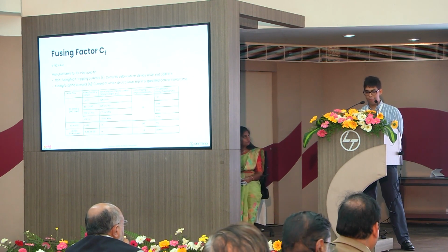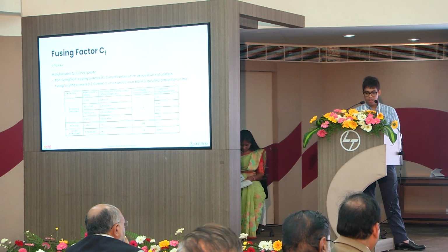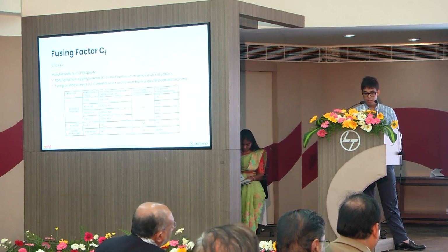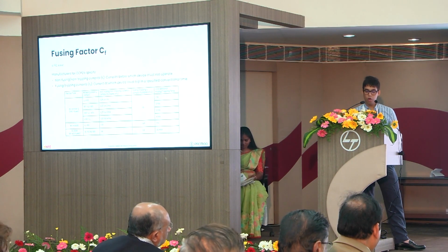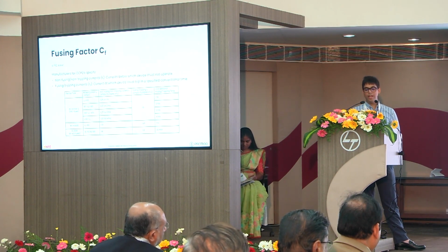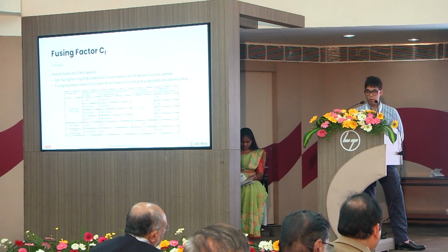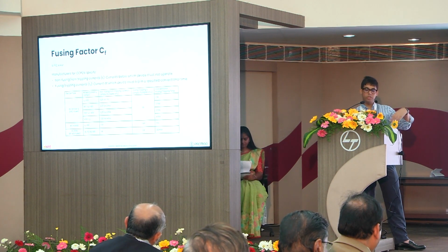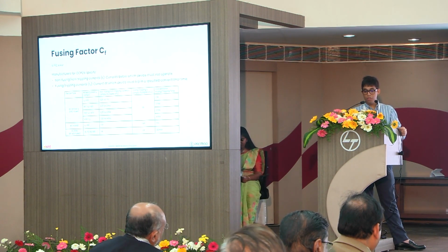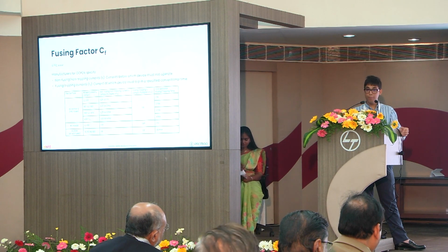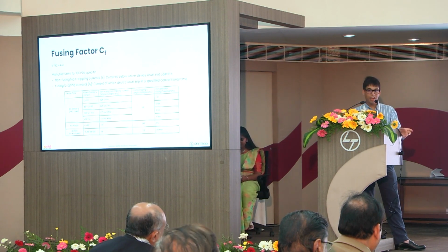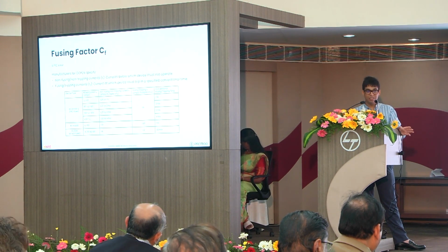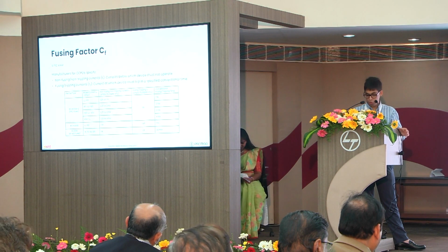Now the interesting one, fusing factor. This is a table that I have put together, looking at all the various product standards as to what the tripping currents and the non-tripping currents are. For 60898 circuit breakers, it is 1.45. Most of the time people forget about that 1.45 because this is taken care of by default. But for HRC fuses, this is 1.6. And for KitKat fuses, your rewirable fuses, this is 1.9. So these will make a massive effect on the current carrying capacity of the cable. They have to be derated.